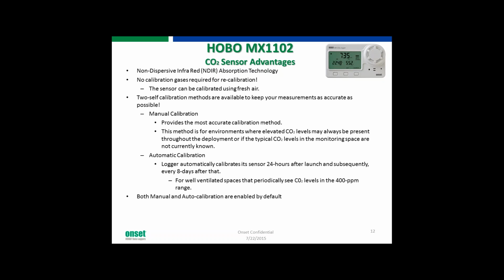Automatic calibration is also enabled by default. Basically what happens is the logger will sit there and it will be logging data, and after the first 24 hours it'll find the lowest point that it saw during that period, take the next 3, average those together, subtract that from 400, and that's how that automatic calibration will be applied, and then it will do that every 8 days after that. Manual and auto cal are enabled by default. When you launch the logger, you can disable either one.